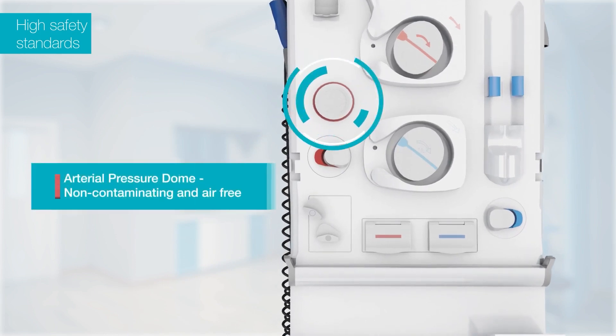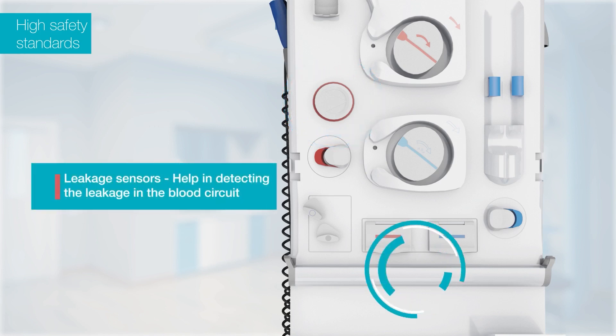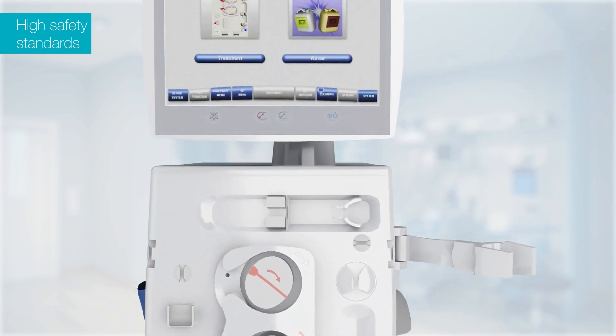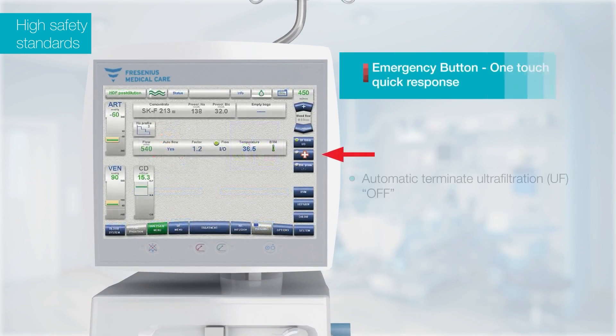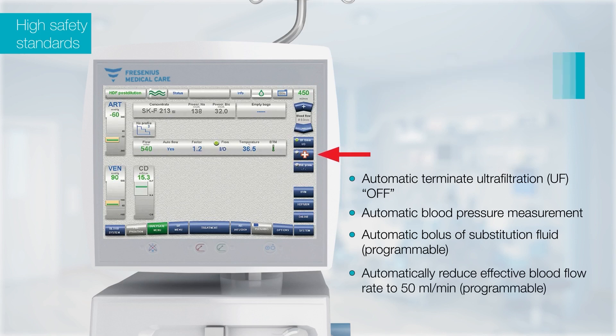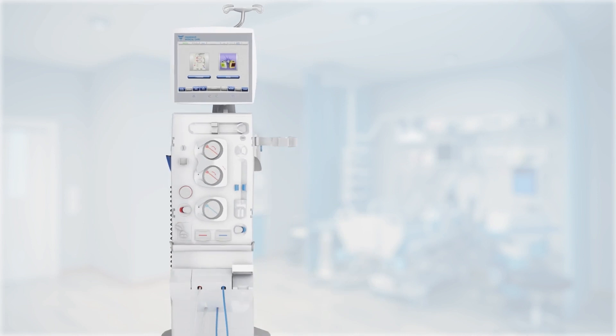A non-contaminating and air-free arterial pressure dome helps in arterial pressure monitoring. The leakage sensors help in detecting leakage in the blood circuit and internal hydraulics, thus preventing potential patient complications. The emergency button provides a systematic one-touch quick response in case of an emergency during treatment, such as severe symptomatic hypertension with obtundation.